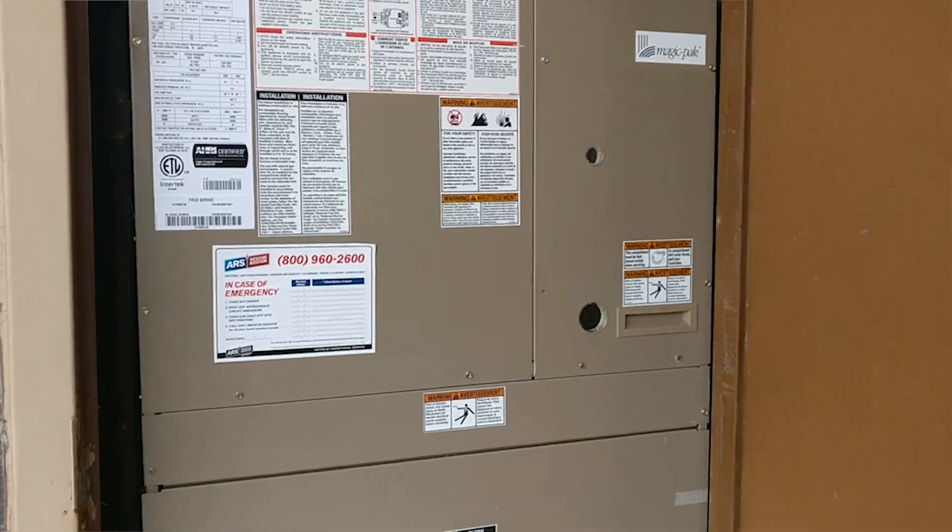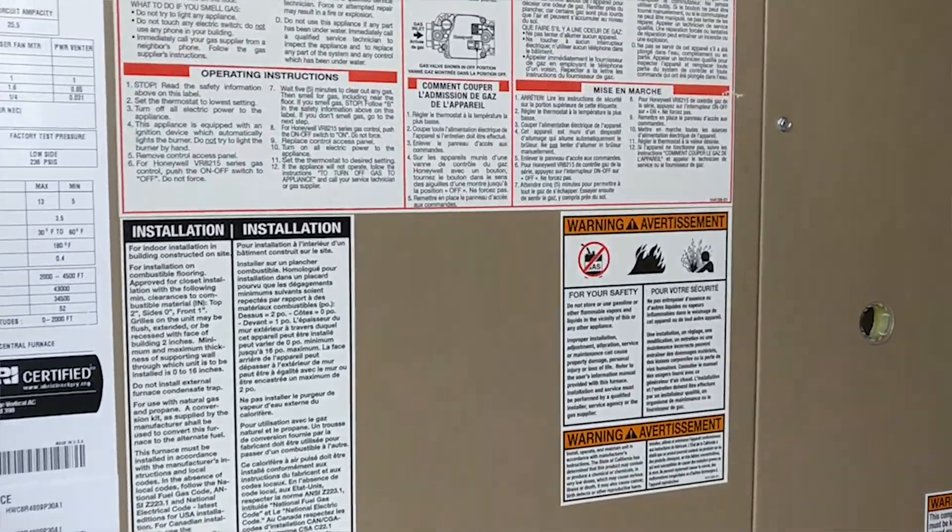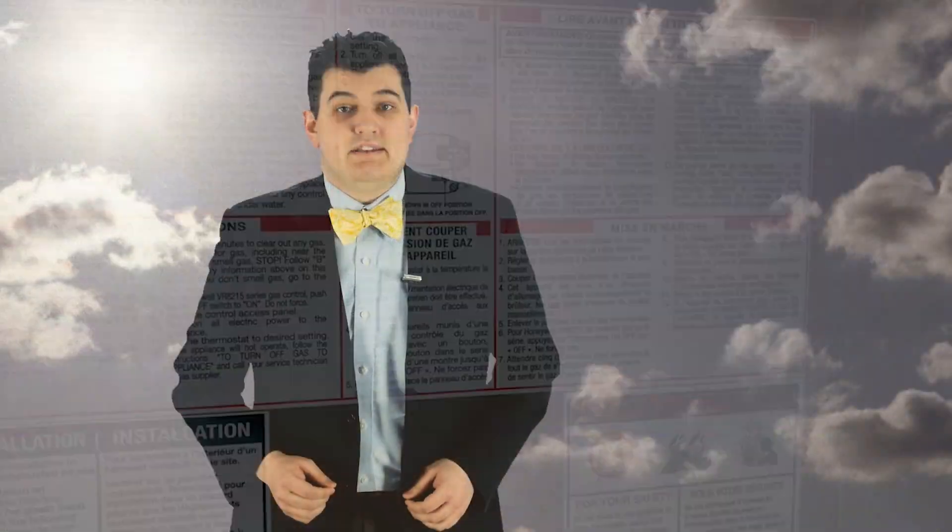For now, a furnace like this is designed to burn a fuel such as natural gas and release the heat of that fuel into the living space. Furnaces are wonderful at doing this. Even the most basic gas-fired furnaces are 80% efficient or more, meaning they release at least 80% of the heat energy contained in natural gas into the living space. In areas that remain cold for a long period of the year, having an efficient furnace is very important. Gas-fired furnaces are usually 80 to 90% efficient.